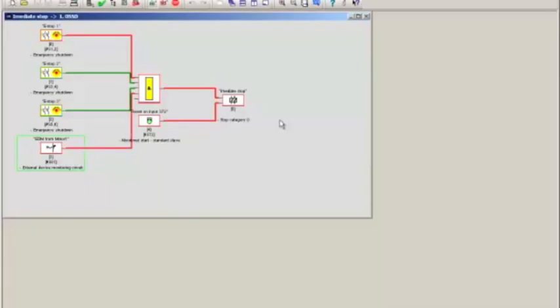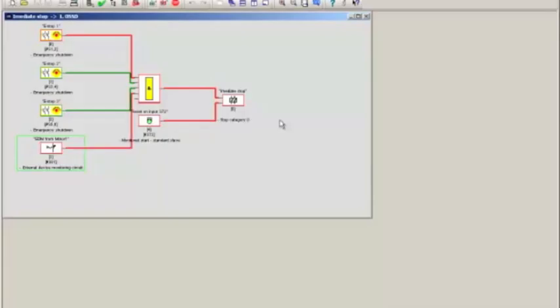And because this was a critical fault, I need to acknowledge this by tapping the set button on the safety controller. The set button is on the front face. It's a little black button, and it just needs to be tapped lightly. And when I do that, the EDM will go back to normal operational mode. And releasing the e-stop followed by the reset will restart the system.